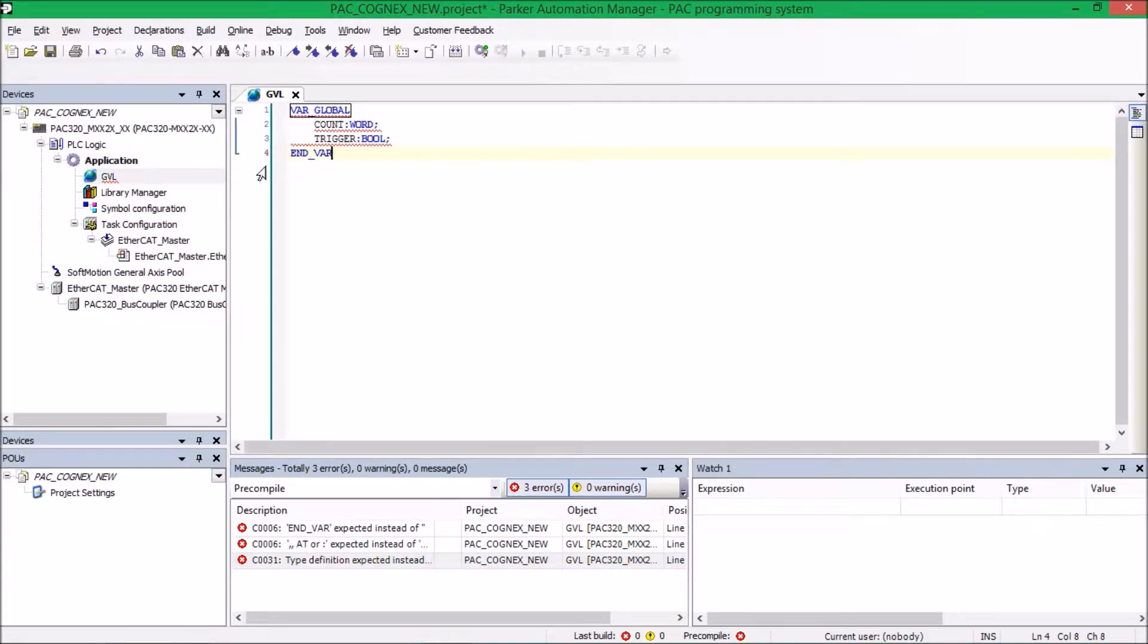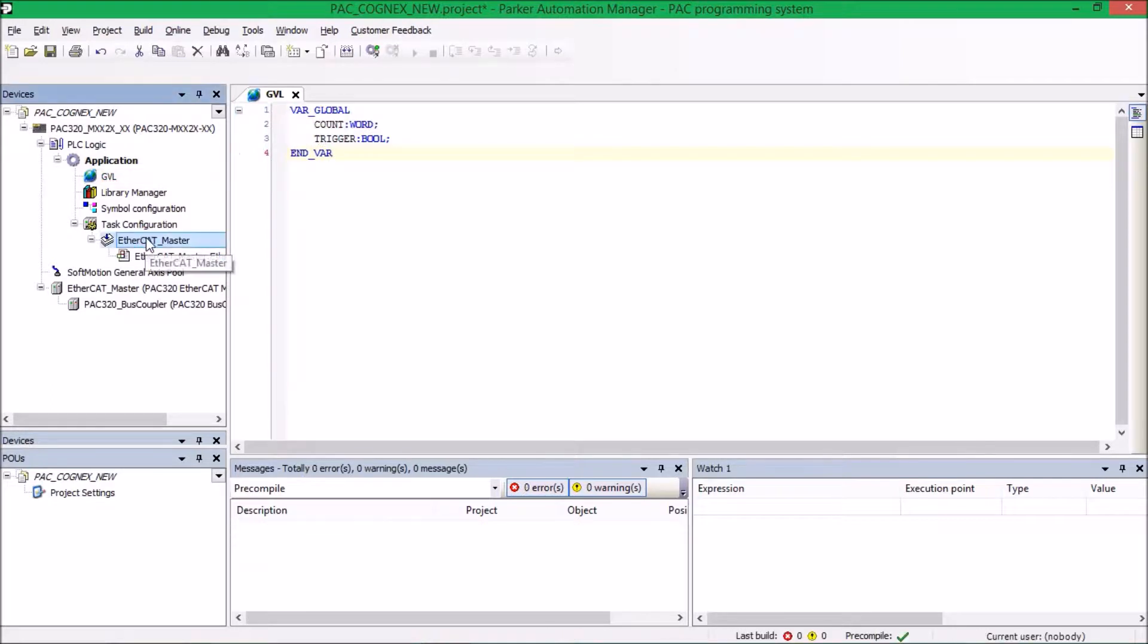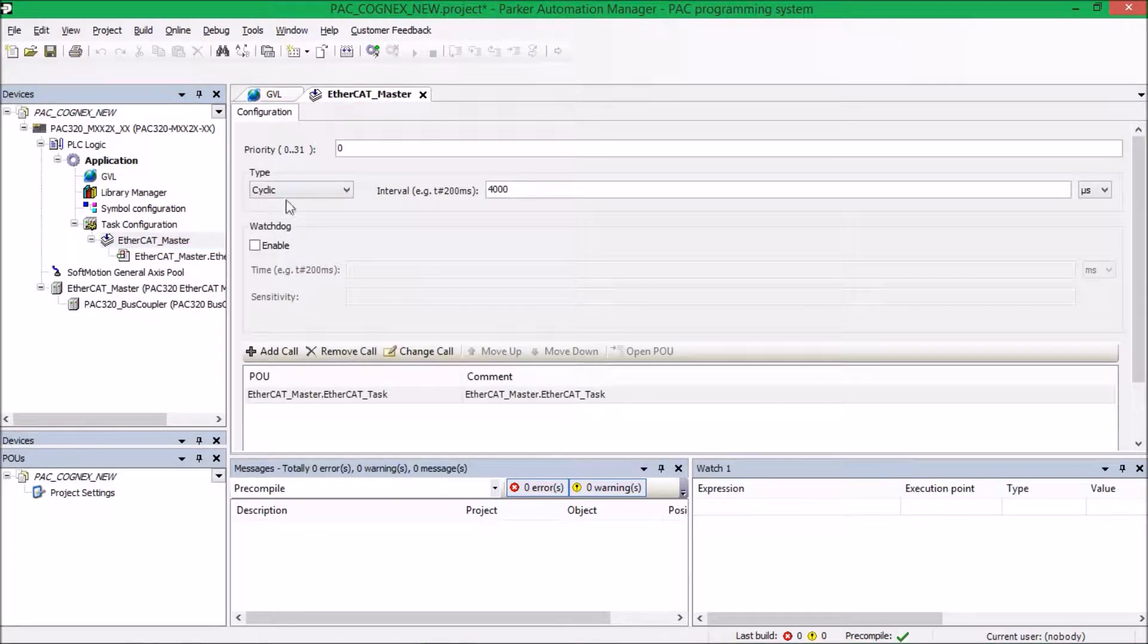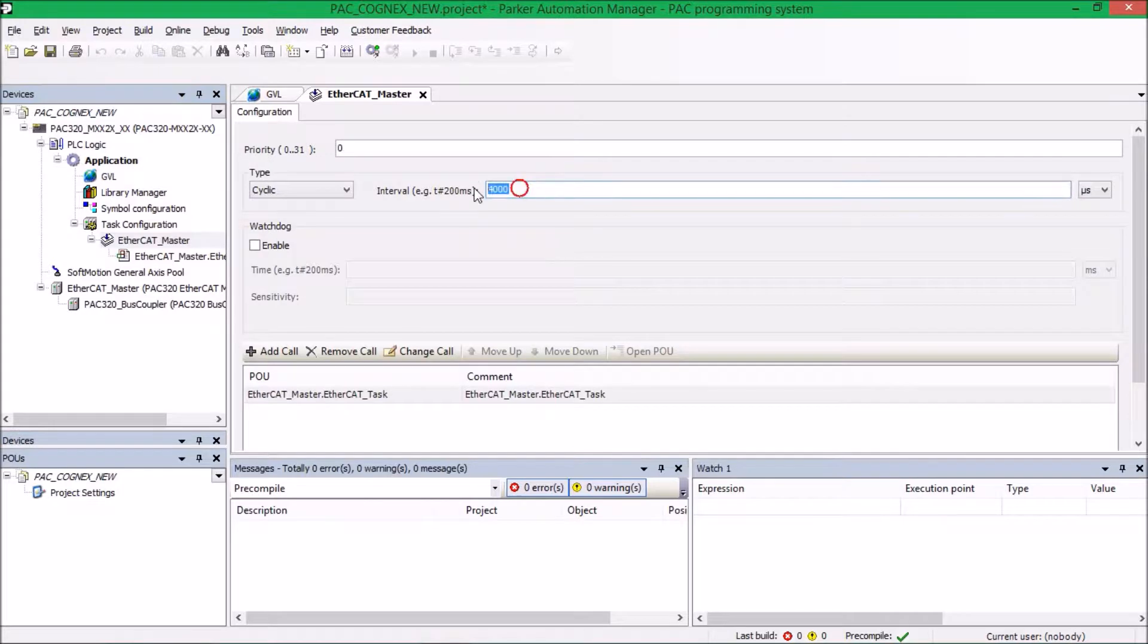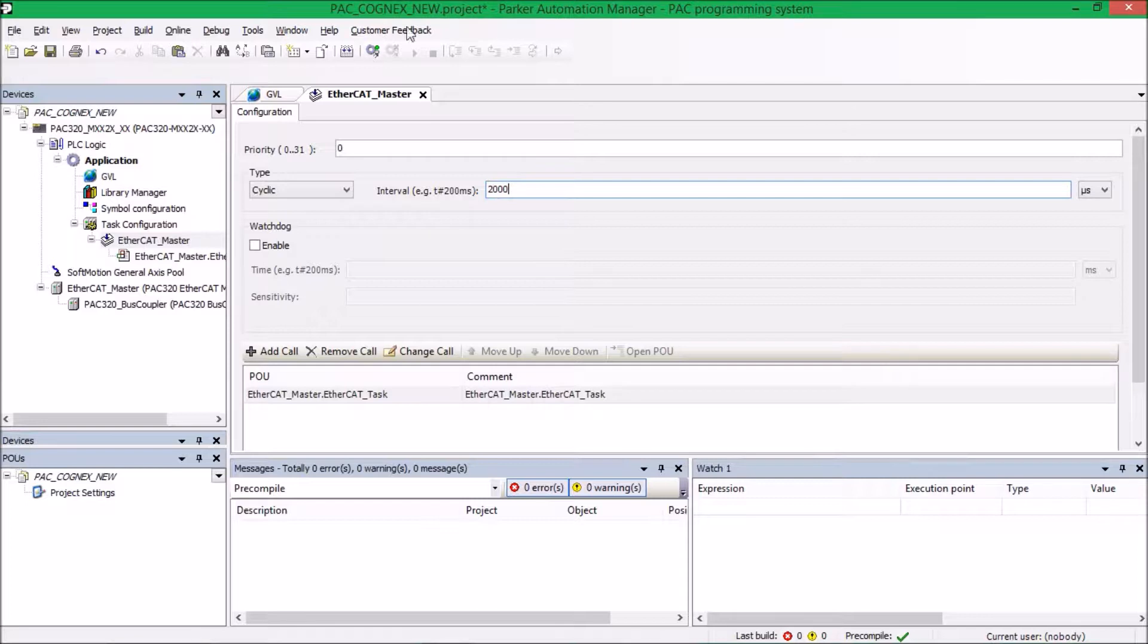So what we're going to do next is we're going to go under EtherCAT Master and make sure it's set as a cyclical event, which it is. We're going to change this interval from 4,000 to 2,000, and it will be saved.